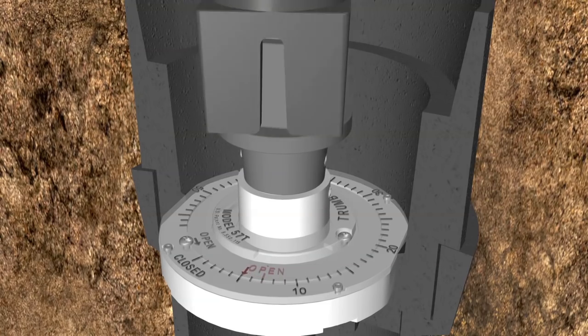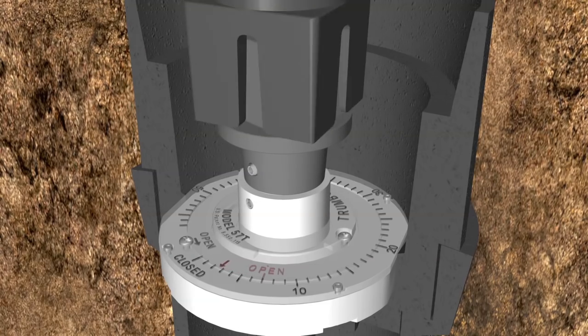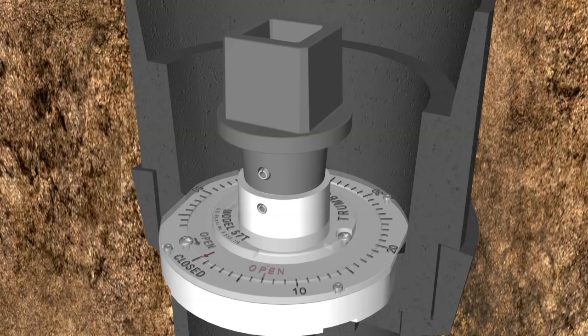Now, fully close the valve. The red indicator arrow should now align with the closed mark on the indicator. If it does, you have correctly calibrated your valve and valve position indicator assembly.